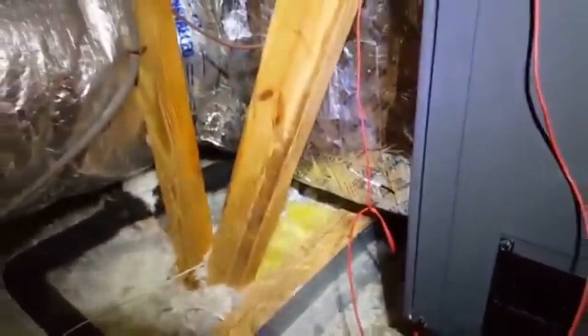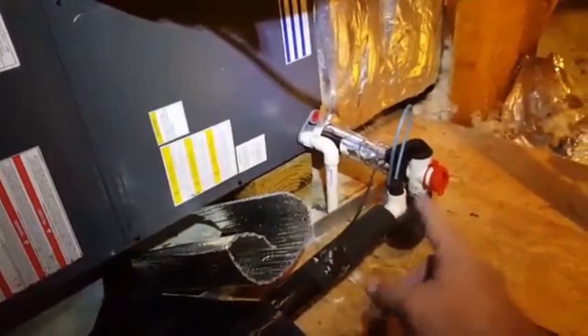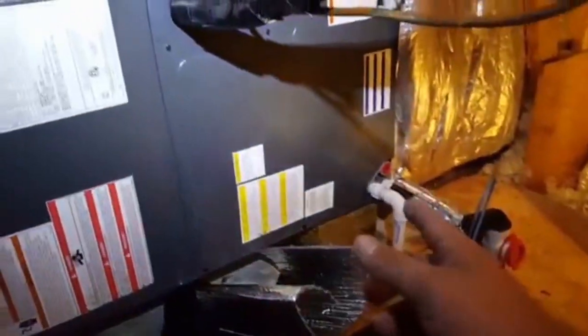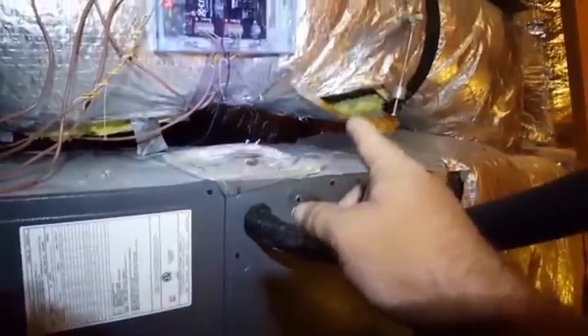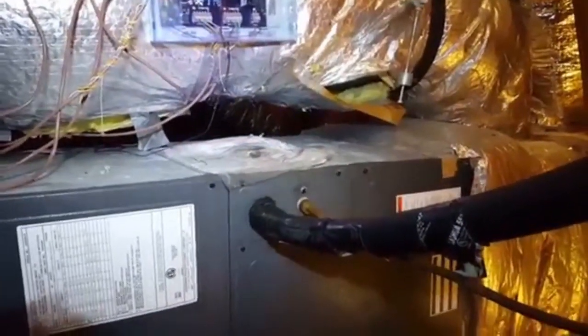Not good, guys. You can see the sweat along the bottom of the air handler here. I've re-insulated the bottom of the plenum, but it's still awful cold coming out, 50 degrees, because of how it's zoned, which I'll explain when I leave. We redid the drain last time, so some other things need to be repaired. I'll probably take that up too, but the bypass is closed, and I'll explain why.